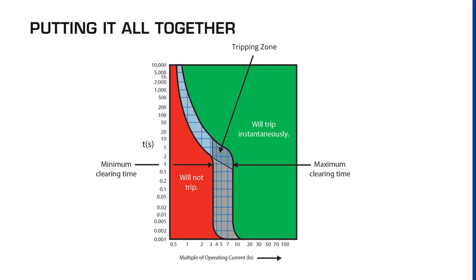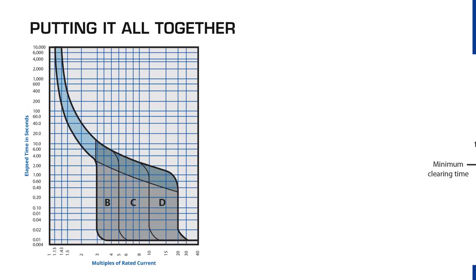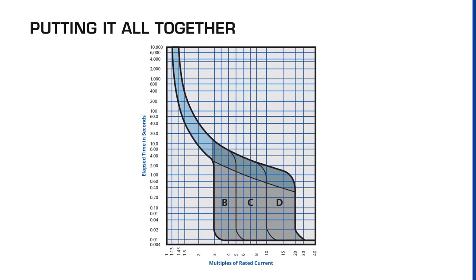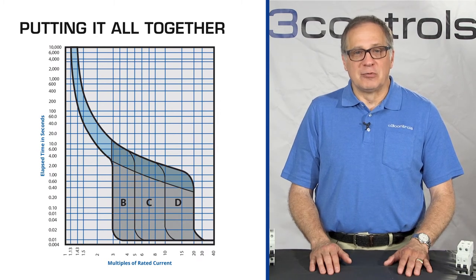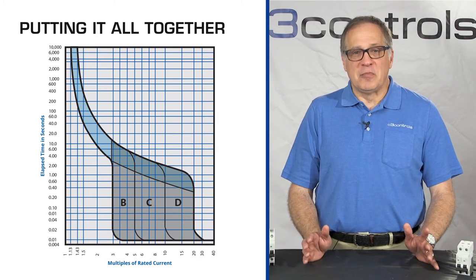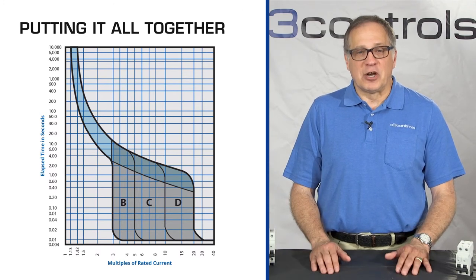Let's put it all together. This figure puts these concepts into a clearer picture. Take special note of the tripping zone where the circuit breaker may or may not trip. The three most common trip curves for miniature circuit breakers are B, C, and D. By putting all three on one chart, we can see how the thermal portion of the curves are similar to each other, but there are differences in how the magnetic coil or solenoid and thus the circuit breaker functions.